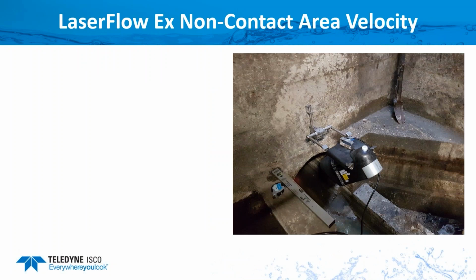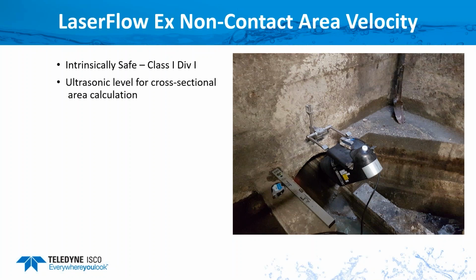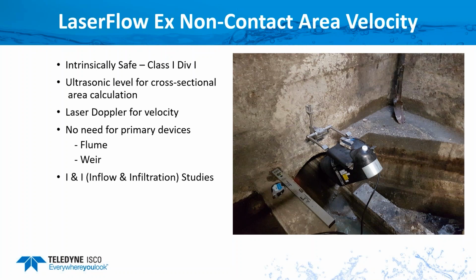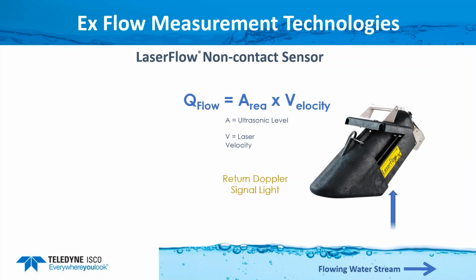Now, other area velocity sensors are the Laser Flow EX non-contact area velocity sensor. It's also intrinsically safe rated, Class 1, Div 1, Zone 0. It uses an ultrasonic sensor to read the level to calculate the cross-sectional area, and uses the laser to measure the velocity. So again, there's no need for a primary device such as a flume or weir. You can use it for inflow and infiltration studies. It can be installed for temporary or permanent applications, and it gives you a high degree of accuracy with the Laser Flow system. Let's take a quick look at how that operates.